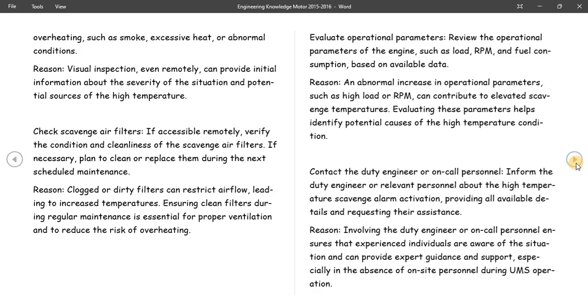So after hearing the sound of the alarm and checking the visual monitoring, next you should check the filters. Sometimes dirt can clog the filters, which may lead to an increase in temperature and might trigger the alarm. The next step, you should evaluate operational parameters. Review the operational parameters such as the RPM and the fuel consumption based on available data. Sometimes an abnormal increase in the operational parameters can lead to such high load. So you should evaluate the operational parameters. If it's supposed to be 50 RPM and you're seeing 40 RPM, there's a tendency that it might trigger the alarm system.